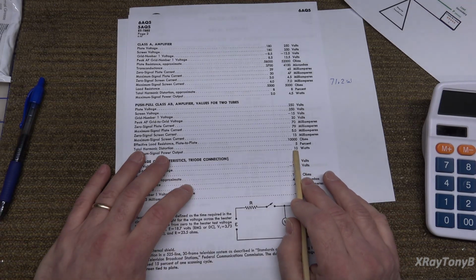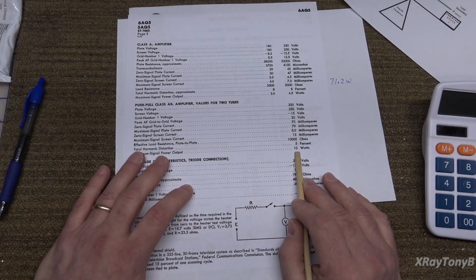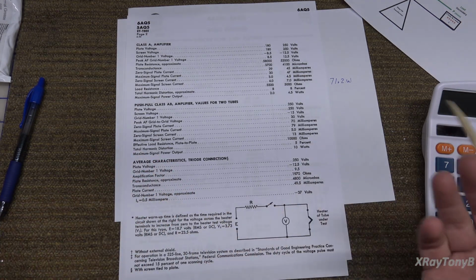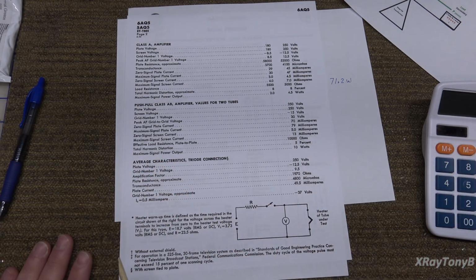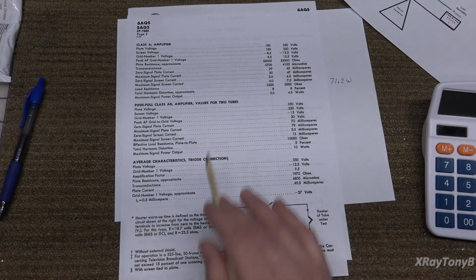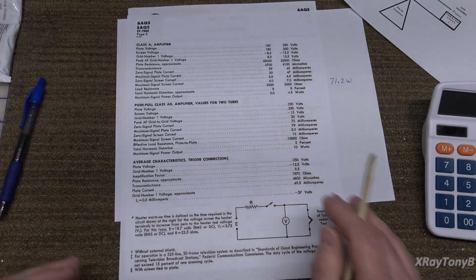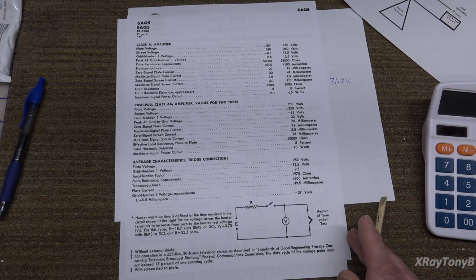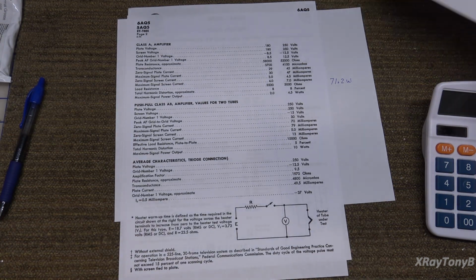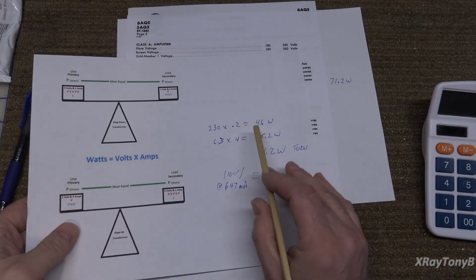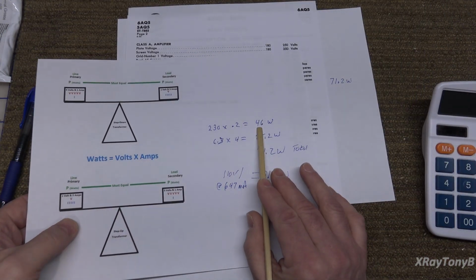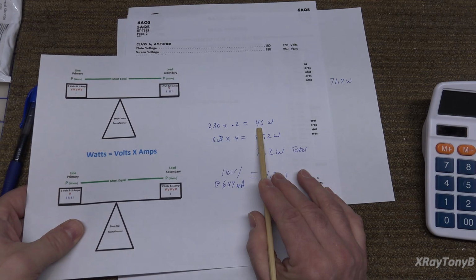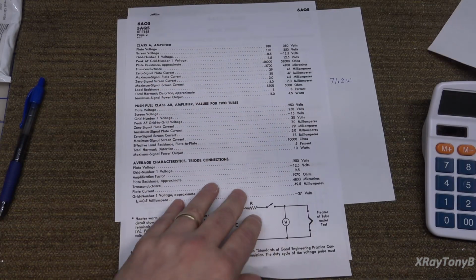So when you add that all up, let's say you have 10 watts for each channel, that's 20 watts. Then we have another, let's say 5 watts for the drivers and for the low voltage things, so that's 25 watts. And if you recall, the maximum we could put on that winding for the high voltage is 46 watts.